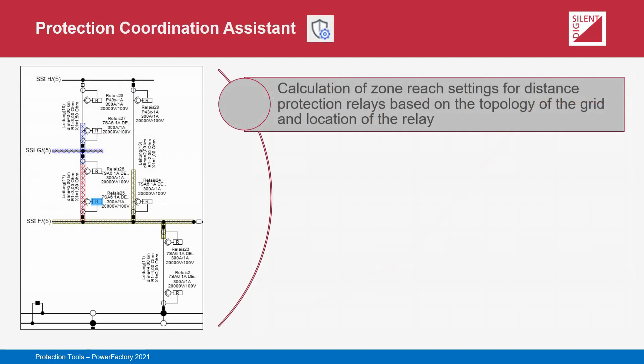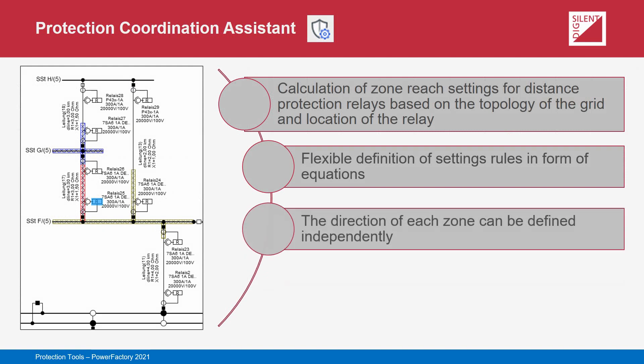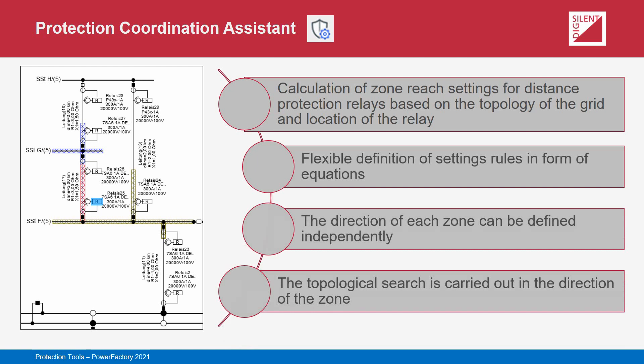The Protection Coordination Assistant is used to automatically calculate reach settings and time delays for the time-distance protection zones of distance relays. For each relay to be coordinated, PowerFactory starts at its installed location and uses a topological search to find the surrounding cables, lines, and other relays which are relevant for the reach and time coordination calculations. From the information gathered, the relevant impedance parameters are then extracted for consideration in the setting rules. The setting rules are a flexible, user-defined set of equations applied to the extracted impedance parameters in order to calculate the appropriate reaches.